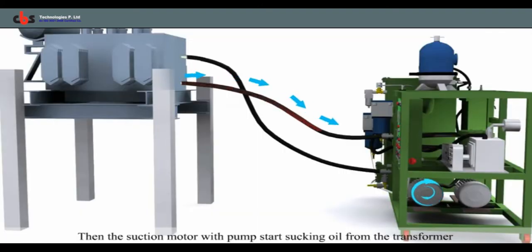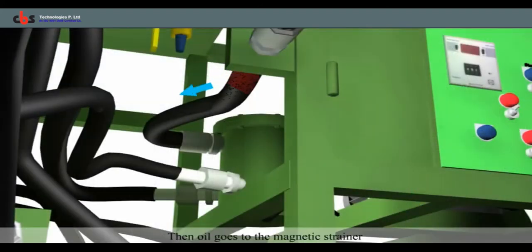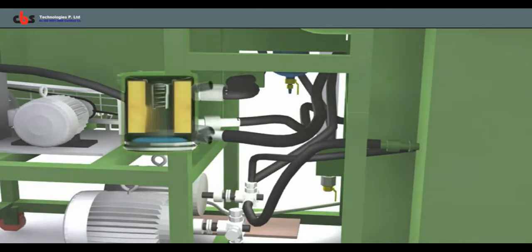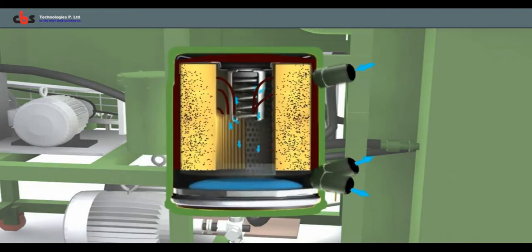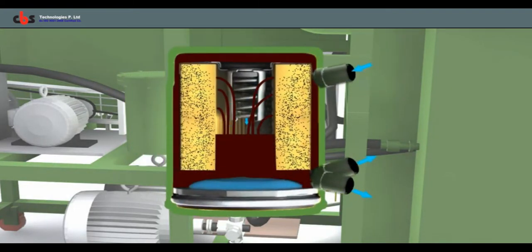Then the suction motor will start sucking dirty oil from the transformer inlet port. After that, dirty oil goes to the magnetic strainer where small metallic iron particles are removed that prevent damage to the suction pump.